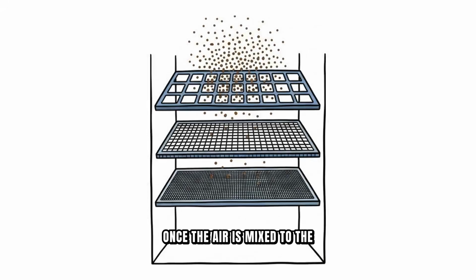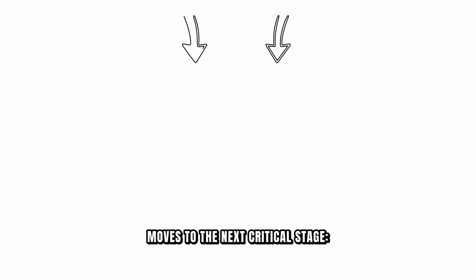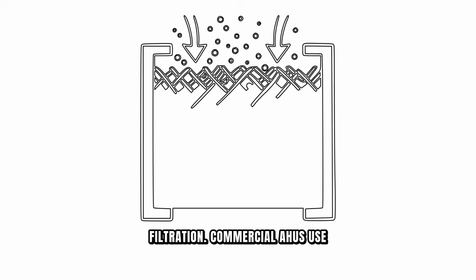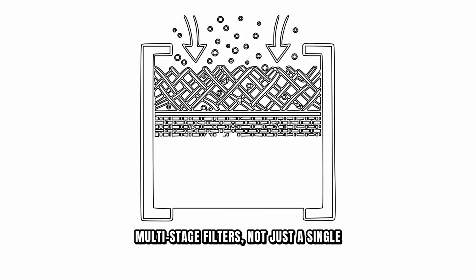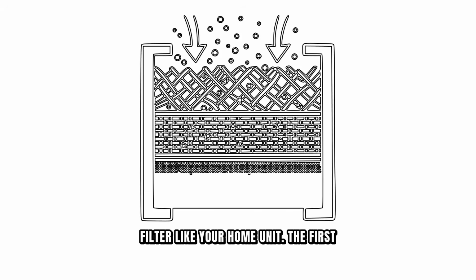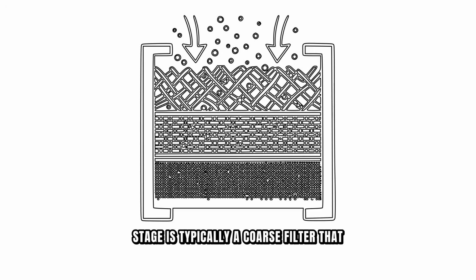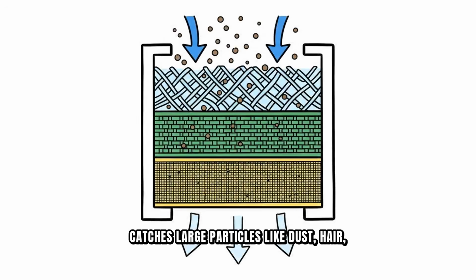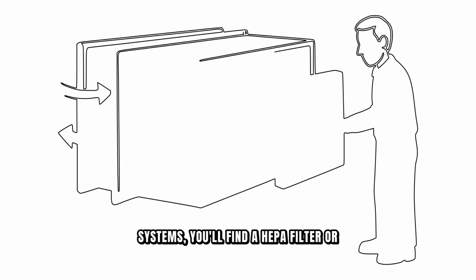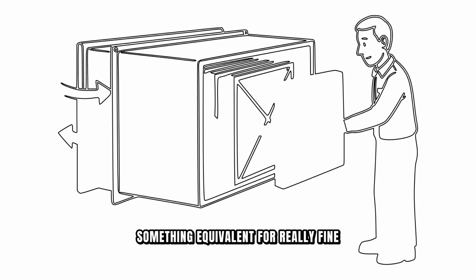Once the air is mixed to the right proportion, it moves to the next critical stage, filtration. Commercial AHUs use multi-stage filters, not just a single filter like your home unit. The first stage is typically a coarse filter that catches large particles like dust, hair, and debris. Then comes a higher efficiency medium filter, and in many modern systems, you'll find a HEPA filter or something equivalent for really fine particle capture.